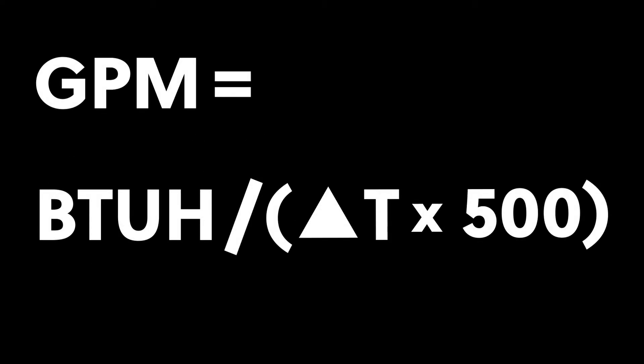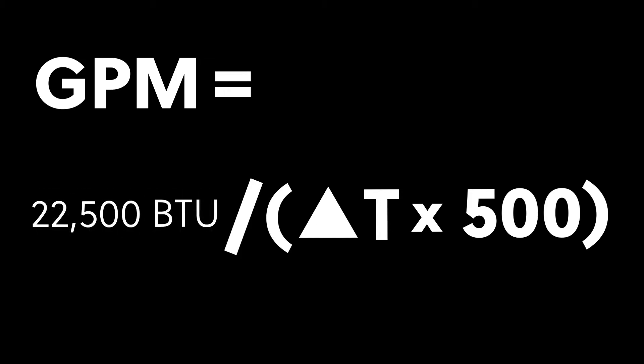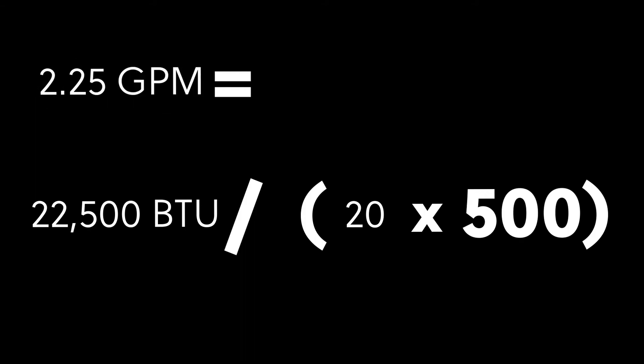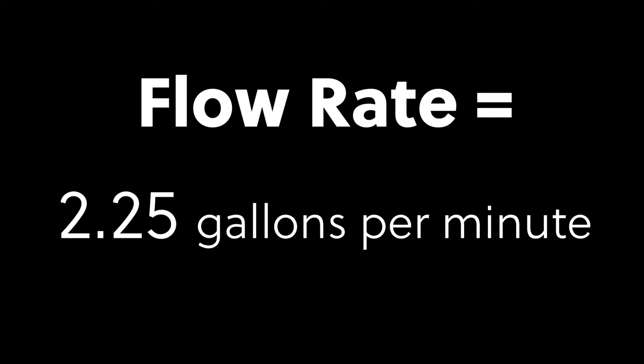So let's plug some numbers into this formula. You've calculated the heat loss of the space to be 22,500 BTUs per hour. We're running baseboard heat, so that's a delta T of 20. When we plug in our load and our delta T, the formula becomes 22,500 divided by 20 times 500, which equals 2.25 gallons per minute. We need to move two and a quarter gallons through this loop every minute.